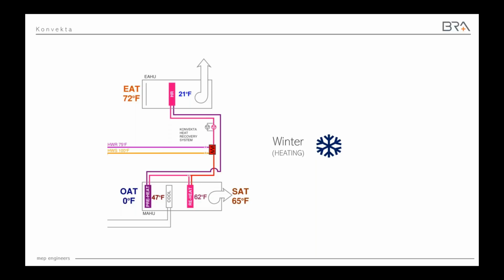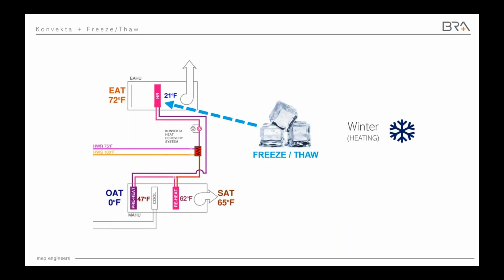Step two on the next slide, and this is getting pretty unique. This is one of the first in the US to do this. We're intentionally frosting the exhaust coil. So that means when it gets below freezing in the exhaust unit and you're trying to pull all those BTUs out of that exhaust air, we're not going to back off on the heat recovery. We're actually going to keep pushing it harder to pull the heat out of the exhaust air, even letting the coil frost. And there's a sequence where the coils frost and defrost, and you can get a lot more BTUs out if you're not limited by that fear of frosting the coil.